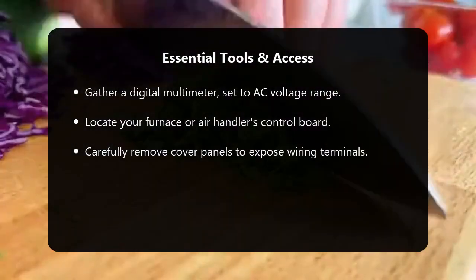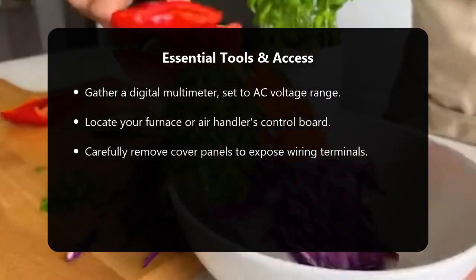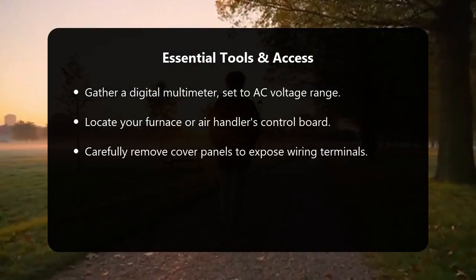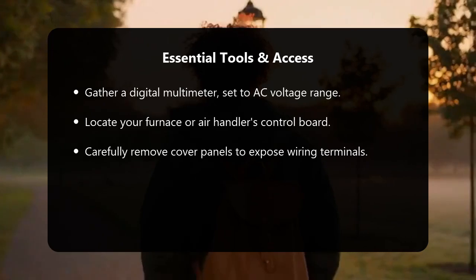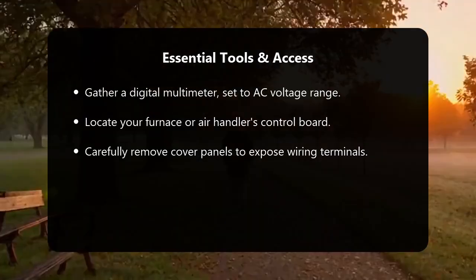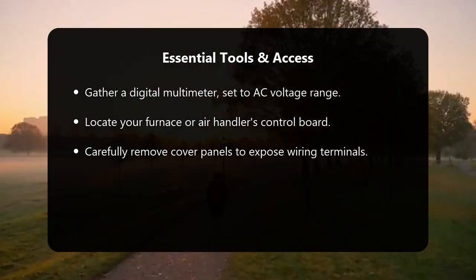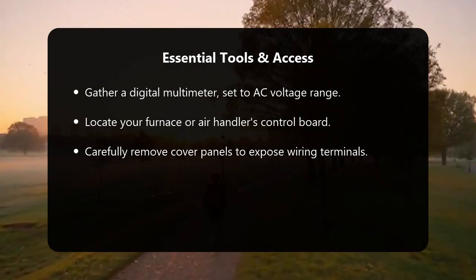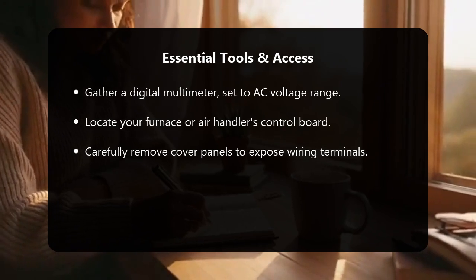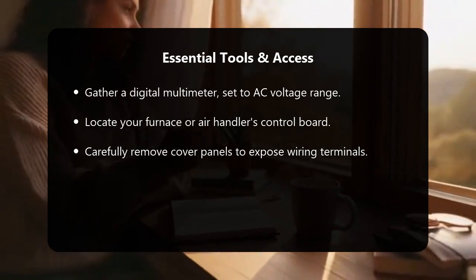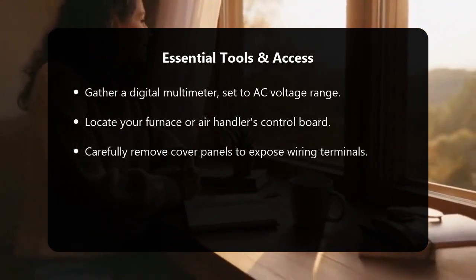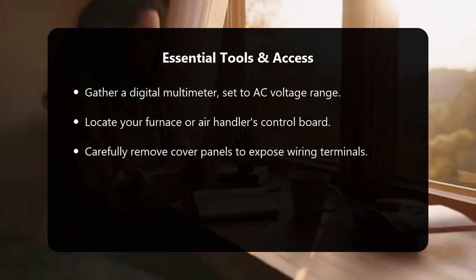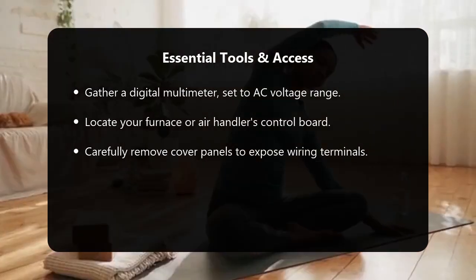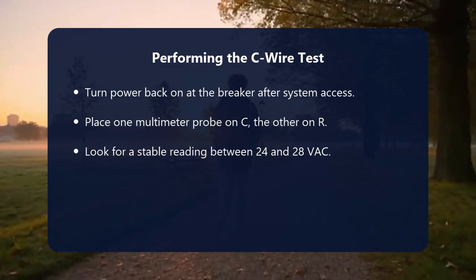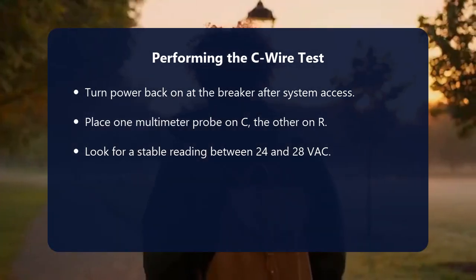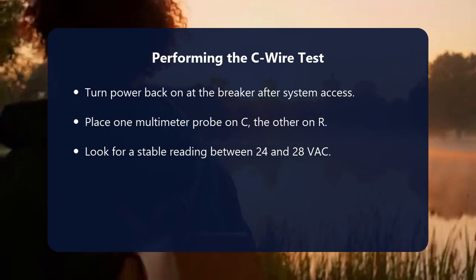On the control board, you'll see various terminals labeled with letters like R for power, often red wire, G for fan, green wire, Y for cooling, yellow wire, W for heating, white wire, and crucially, C for common, often blue wire, but wire color isn't always definitive. Once you've identified the C terminal and the R terminal, sometimes labeled RH for heating or RC for cooling, but they generally serve as the 24V power source, you're ready to perform the test.